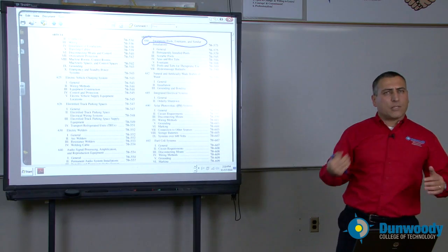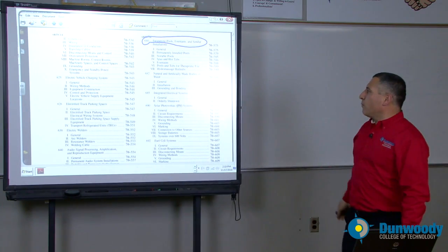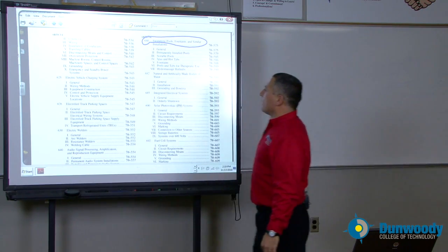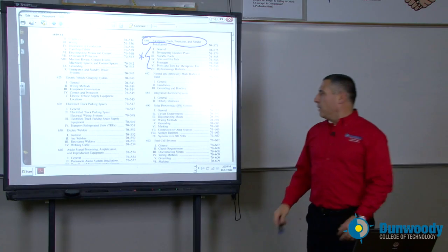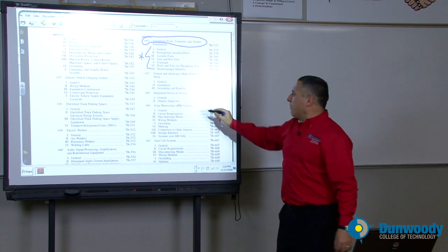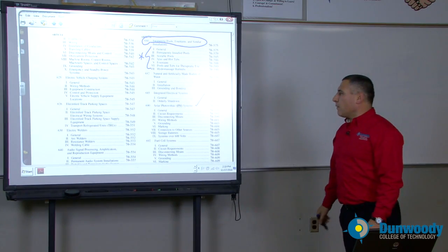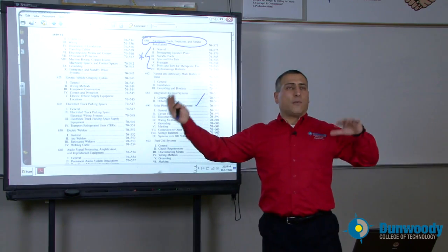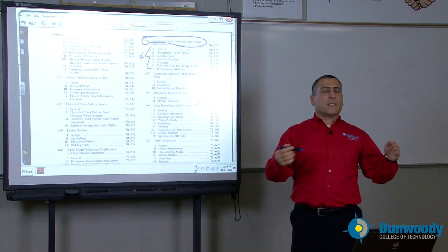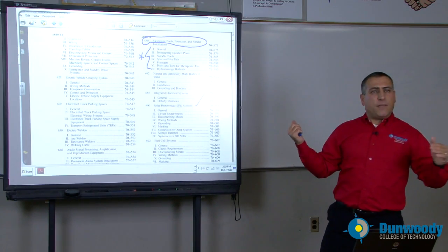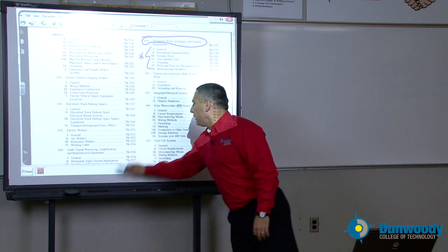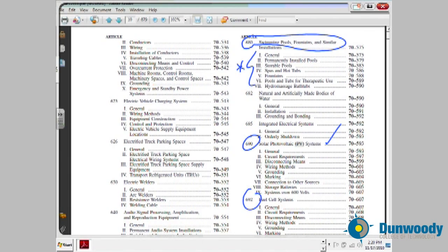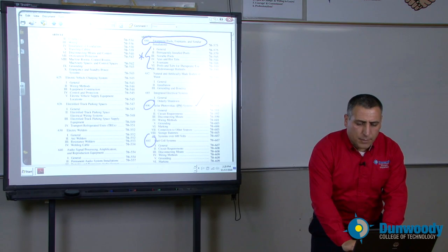If you have to wire a swimming pool, it's different than wiring your bedroom. What type of wire do you use? How do you ground the swimming pool? How do you do an equipotential grounding system for the swimming pool? All this information — covering swimming pools, fountains, spas — is a great article to review. For green energy, if you have a PV solar photovoltaic system, how do you wire it to a building? Can you mix the DC wires with the AC wires? All this information is in article 690, and also fuel cells.